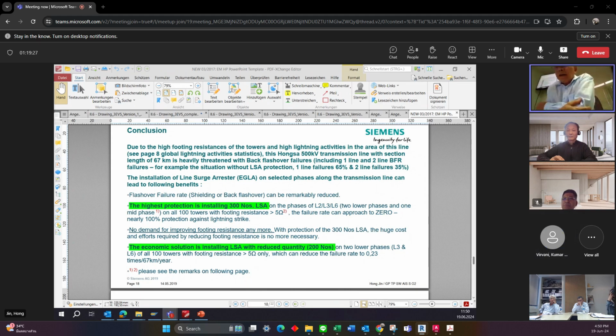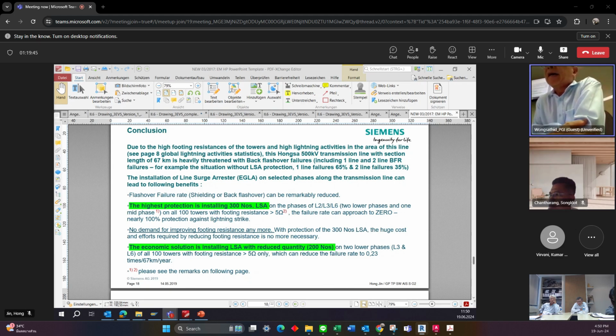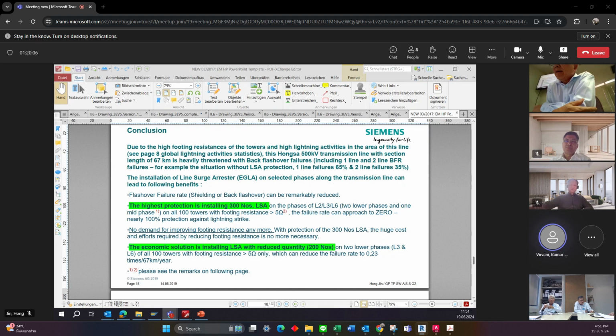Thanks. Normally in many of the reference technical papers, they refer to magnitudes of about 100 kA maximum. But from your technical specification of your arrester, it seems that the maximum nominal discharge current is 20 kA. Is that the same thing or a different thing? No, it's actually different. I can say it's the waveform of a surge arrestor. The maximum nominal discharge current has a waveform of 8 by 20 microseconds, but the lightning impulse waveform is 1.2 microseconds divided by 50 microseconds. So it has a different wave shape and will differ in terms of magnitude also.